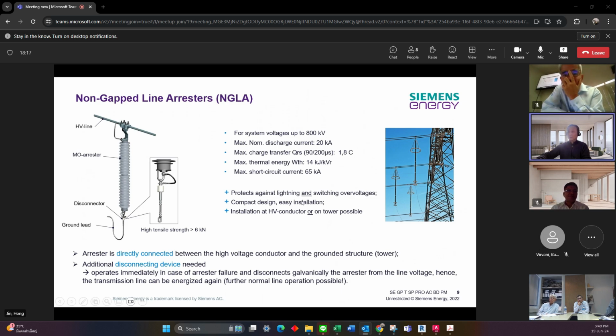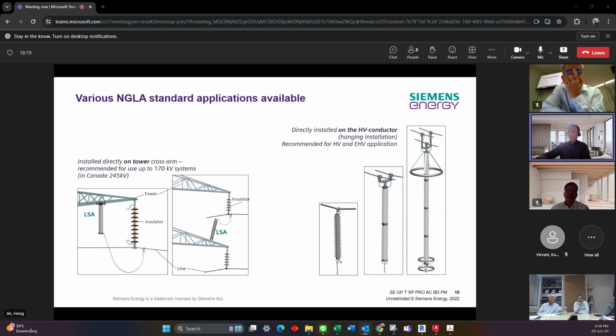So for the non-gapped surge arrestor, like a normal substation surge arrestor, it will take a certain quantity of the MOV inside. It will withstand constantly operating voltage, and it has a certain requirement for the withstand voltage and also for the creeping distance, pollution level, and so on.